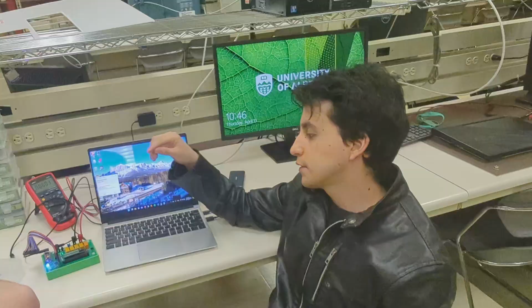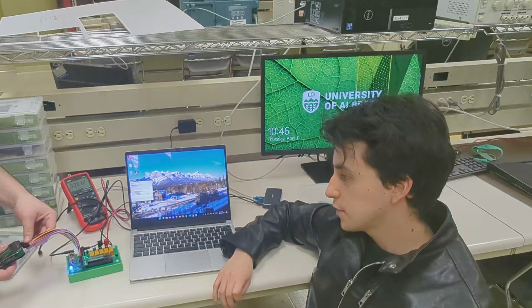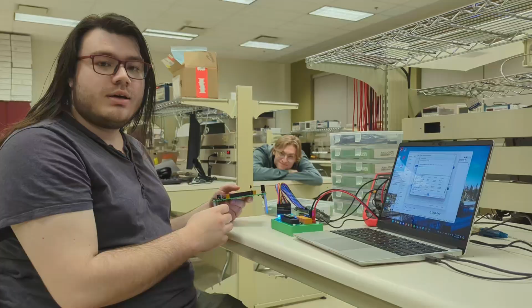Well, hey, would you look at that? It's already finished calibrating. So as you can see here, there is no need for human intervention during the calibration process. All it takes is for the end user to connect the Analog Discovery 2 or 3 devices to this calibration board, and then they can just press this button here and start the calibration. So with this, we have achieved a fully automated system for calibration, and we've achieved, as you can see here, roughly about 1.5 minutes of calibration time, and thereby we save a lot of time.